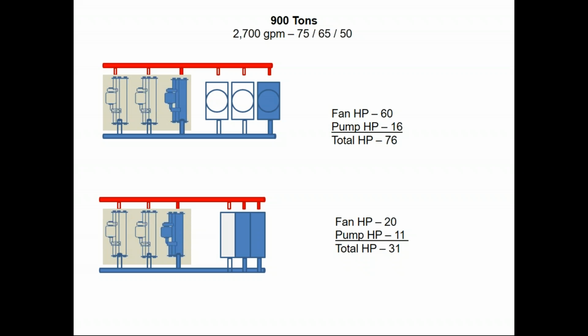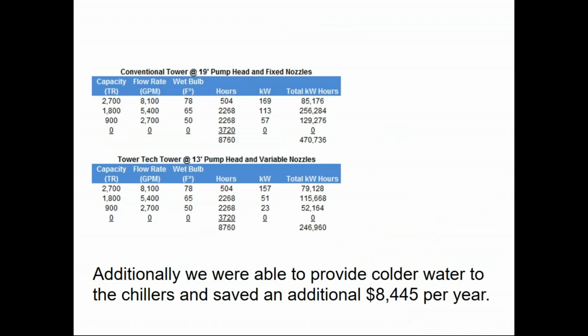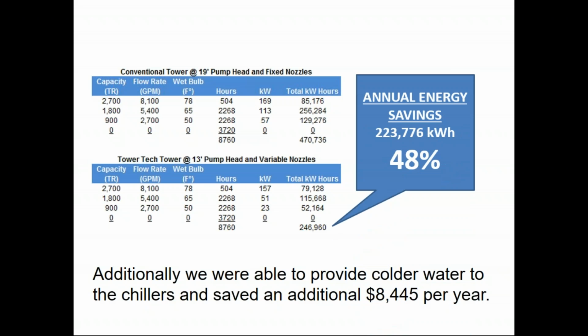At 900 tons, the traditional tower system, again, we turn off a chiller, we turn off a cell, and they're operating at 76 horsepower. There's a certain point where we can't operate one chiller through 3 towers. So we're going to turn off a cell, and at that point we have 1 chiller operating through 2 cells, and in this case we're operating with a total horsepower of 31, and this is a 59% energy savings at that point in the chiller plant. So when we do the full analysis overall, we had a 48% energy savings over a traditional tower system.